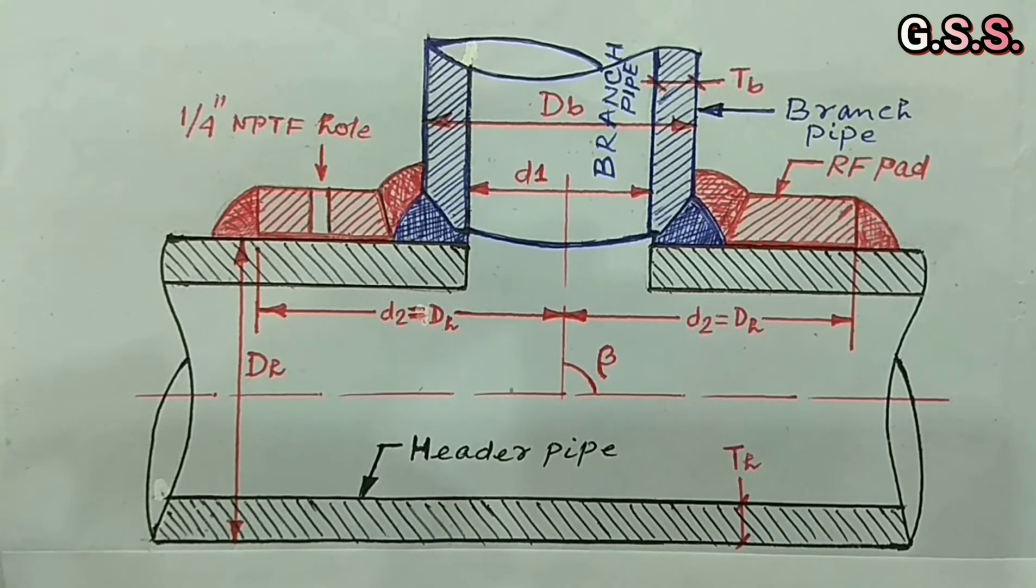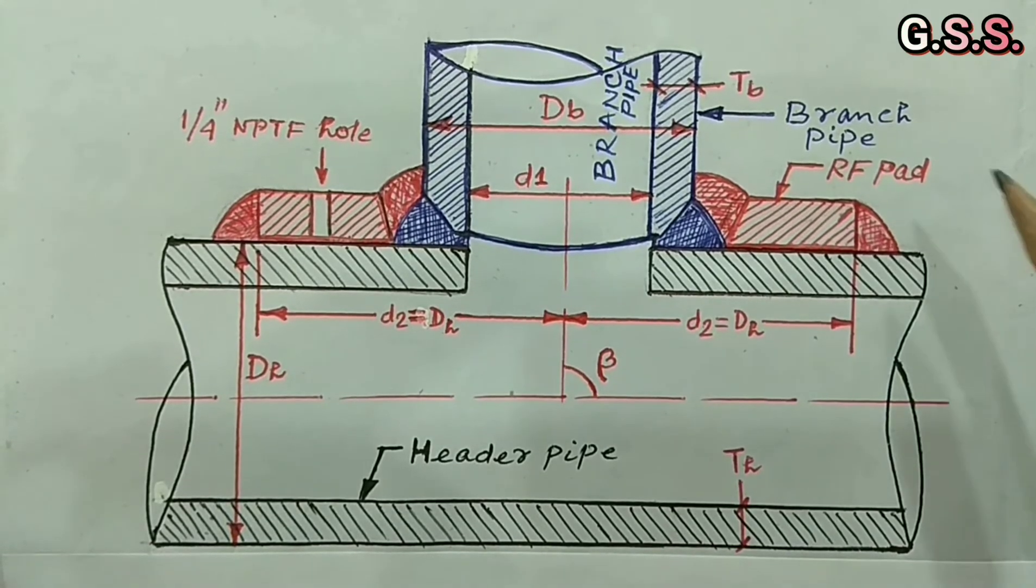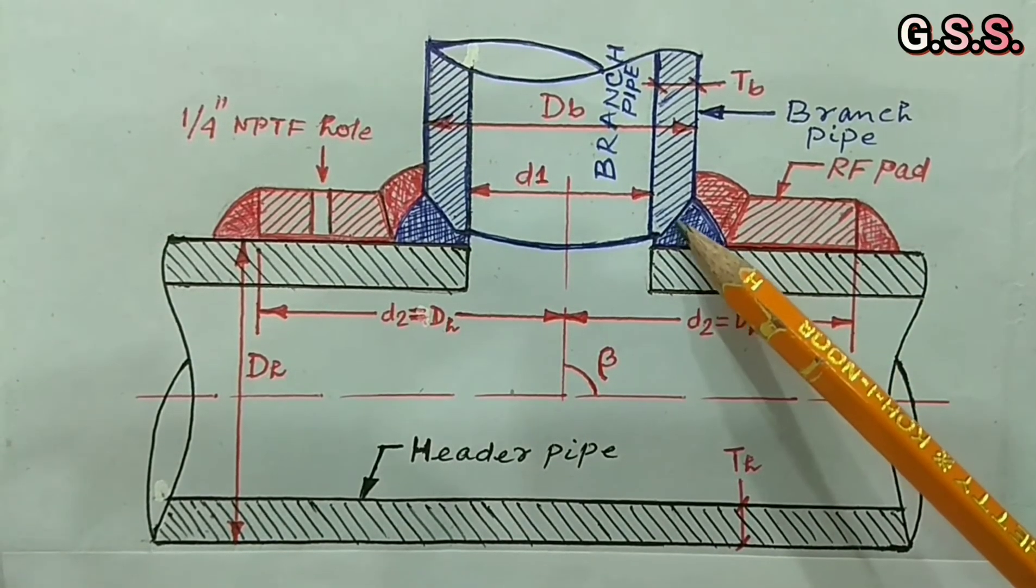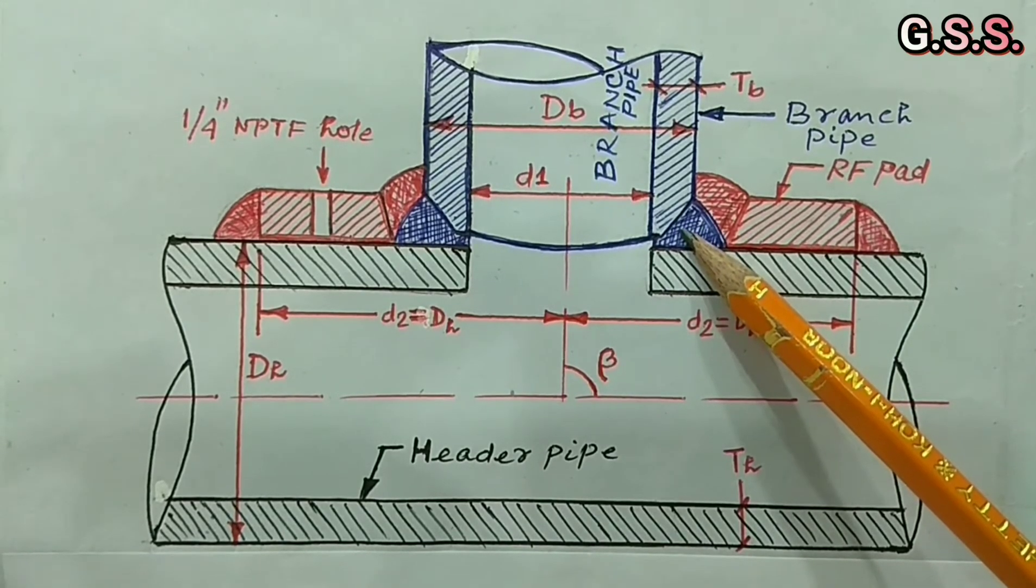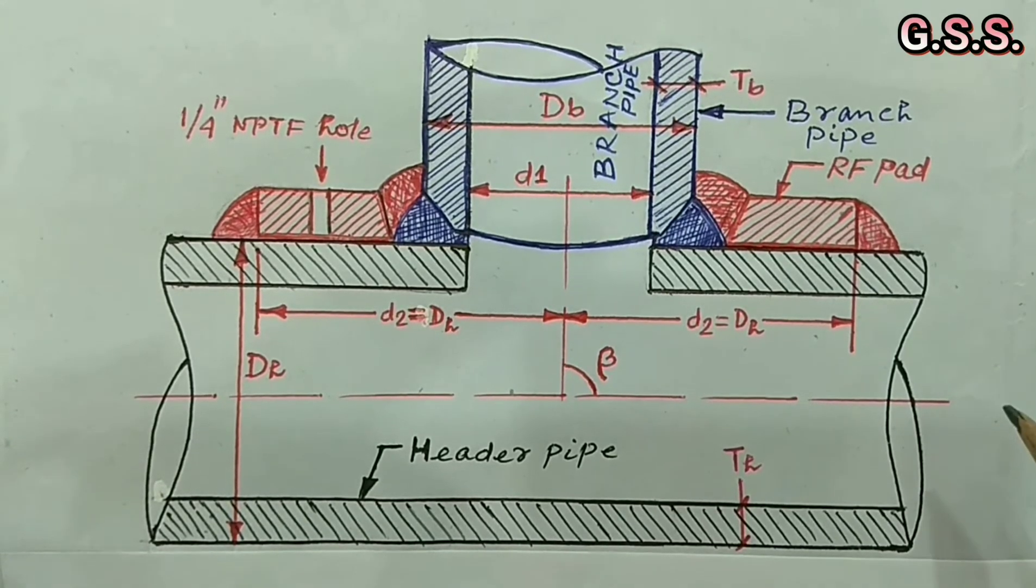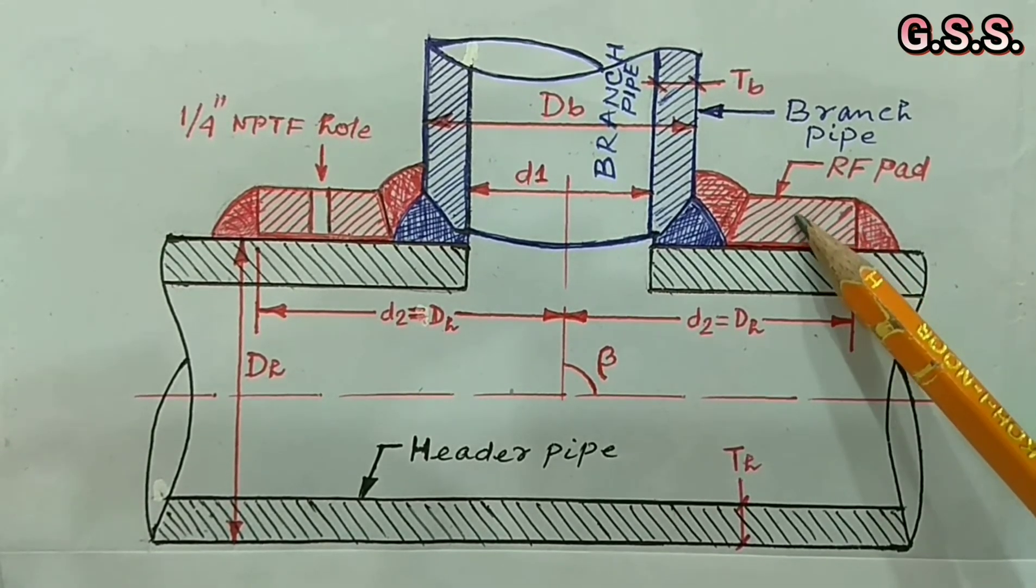First we should consider direct branching without any RF pad, that means unreinforced branching. If it is OK from internal pressure and pipe stress point of view, then no problem. Otherwise we have to go for branching with RF pad.